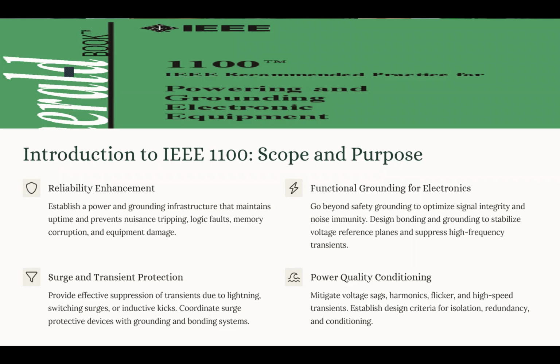We also would have protecting equipment from physical damage that could happen because of power surges or harmonics. Now, another objective for this standard is functional grounding for electronic devices. As we said, the traditional grounding is mostly focused on safety, so it's basically focused on clearing faults and protecting people. But the functional grounding that we want to talk about creates a stable, low impedance reference plane for the signal circuits. One of the key functions of this type of functional grounding is signal integrity, which is reducing the common voltage differences between systems to prevent logic errors.